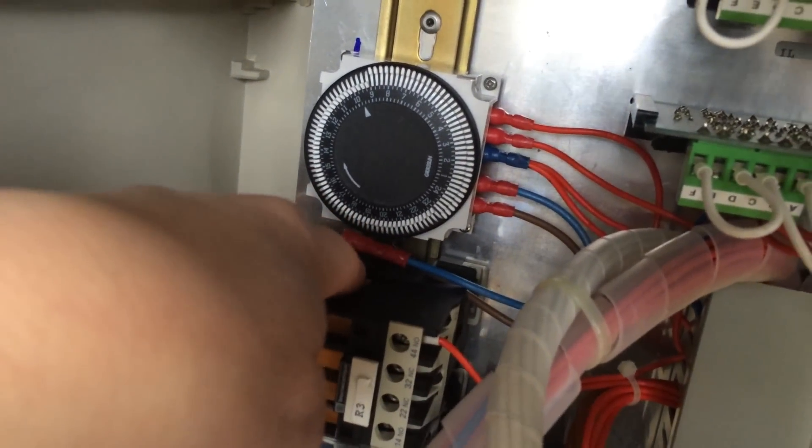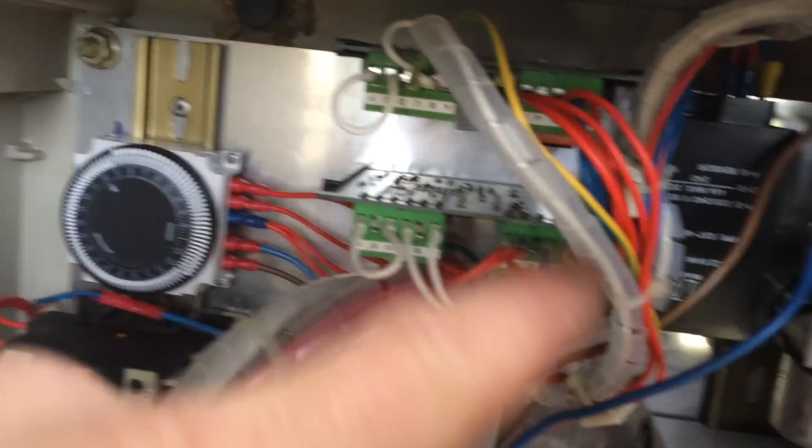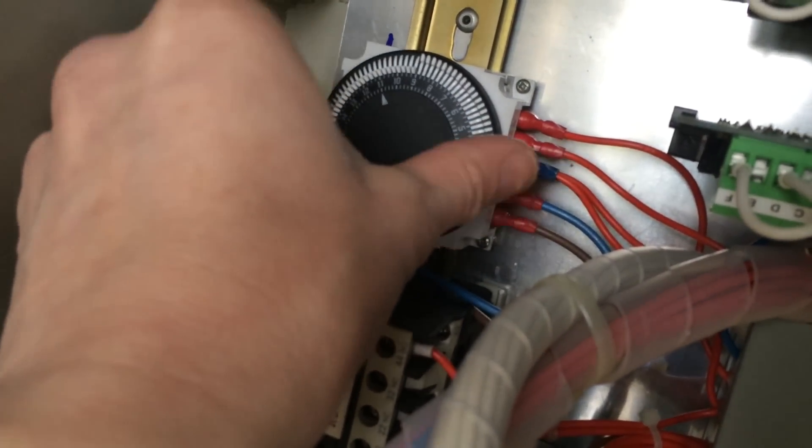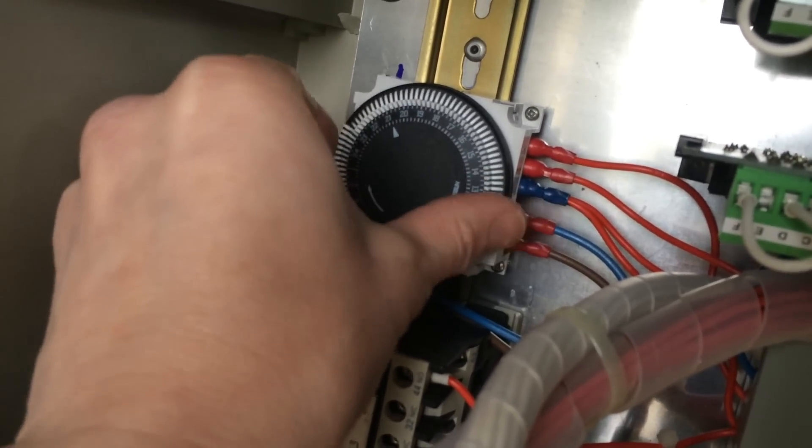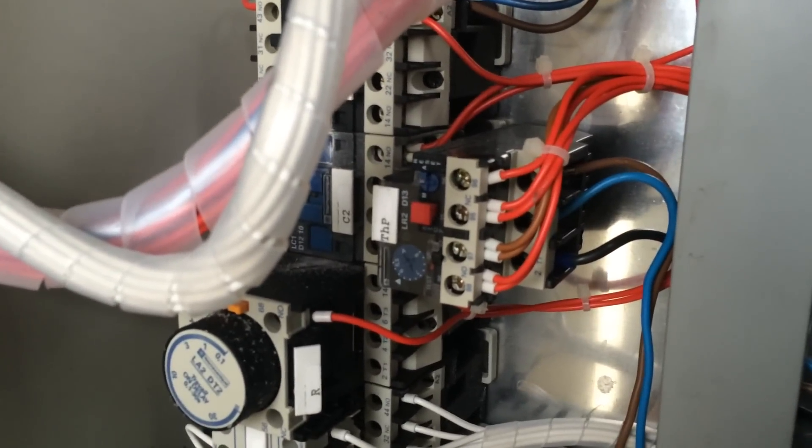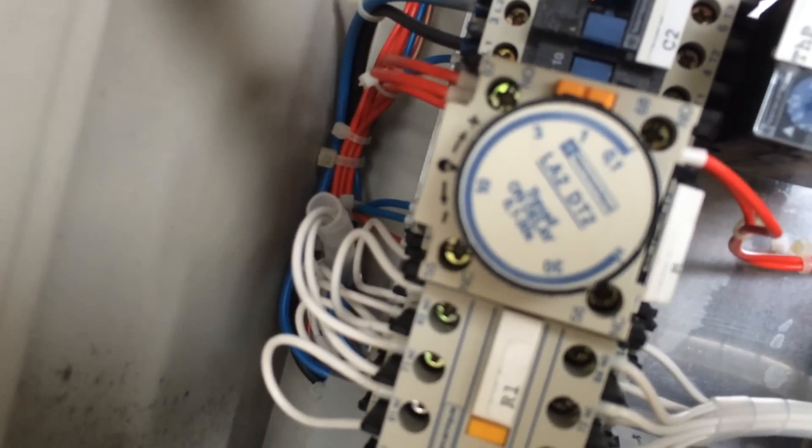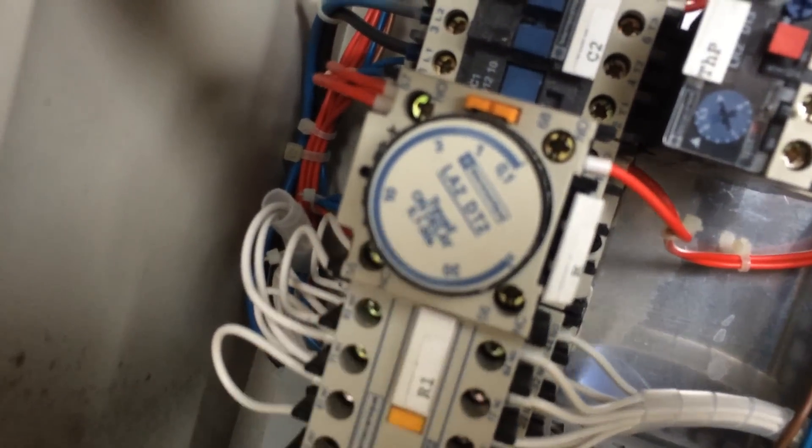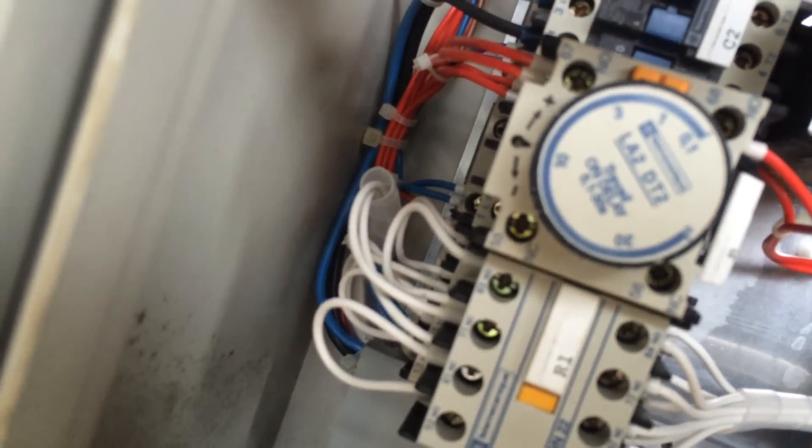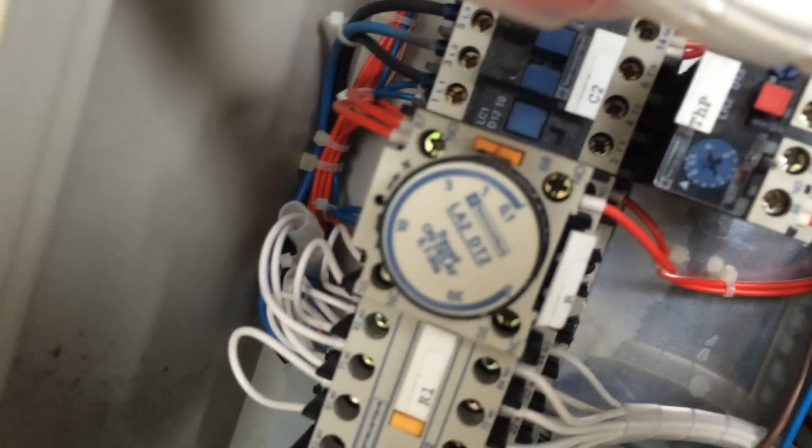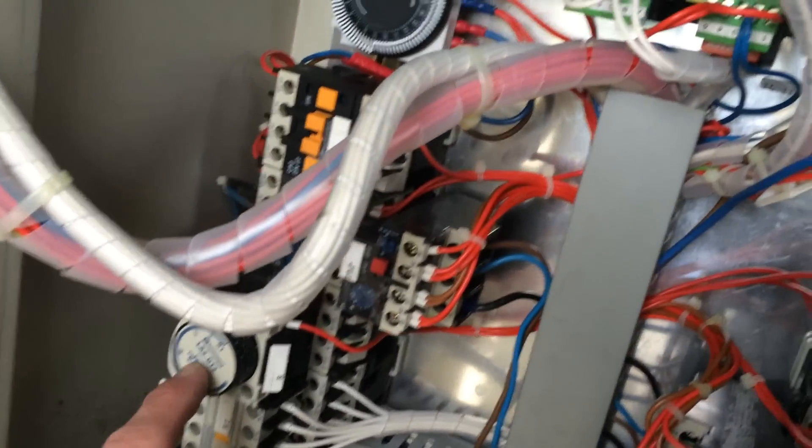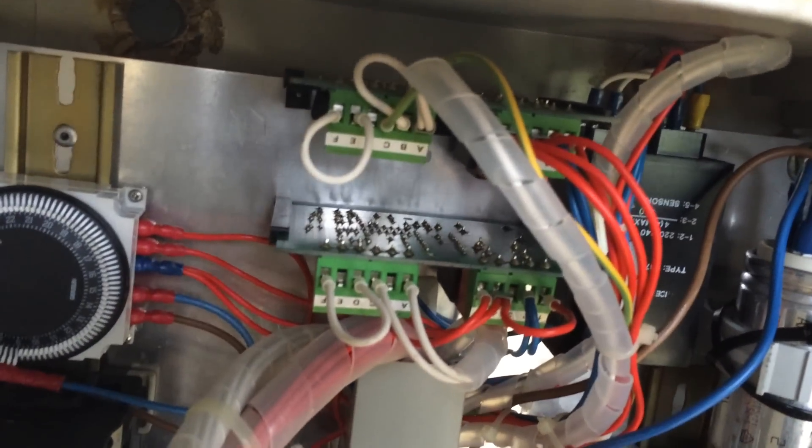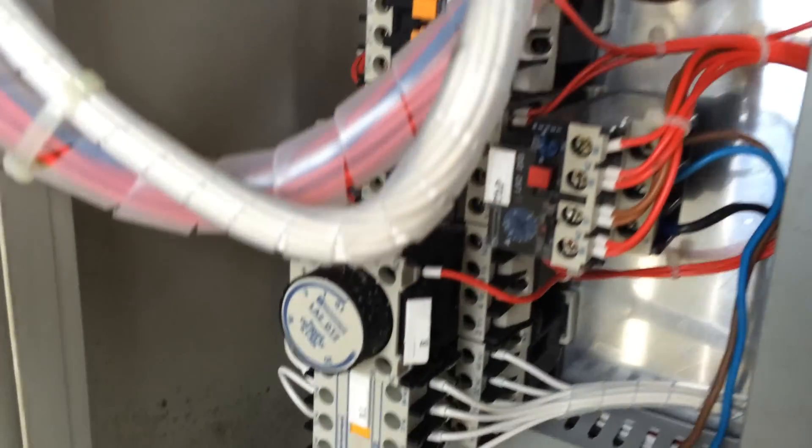Because that contactor pulls in when the ice pack controls drop out. Turn that down to midnight at 11 o'clock. That pulls in. This one pulls in. And I think they're running the second ice pack control off of this delay timer here. It's a pneumatic delay timer which is set about 10 seconds, I think. And it takes quite a bit longer than that. So I think we'll get another one of these ordered up, because if that's not working, then we're never going to get any power on to the second ice pack control. So that could be another problem.